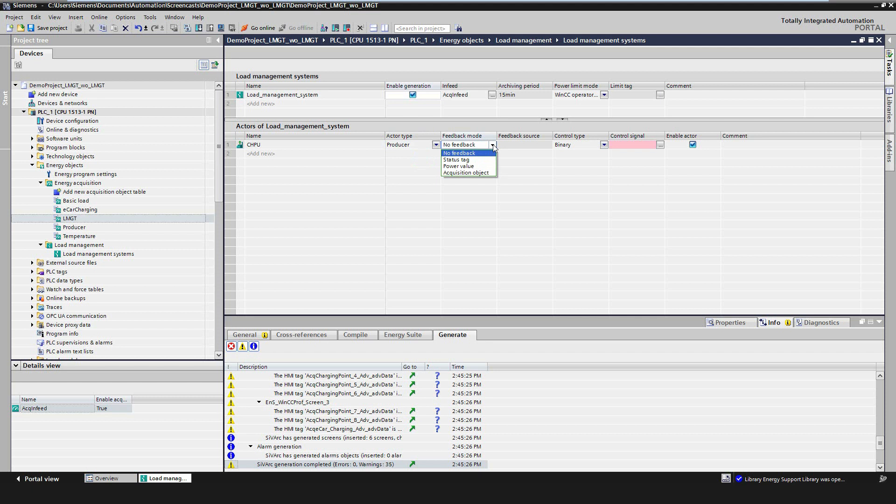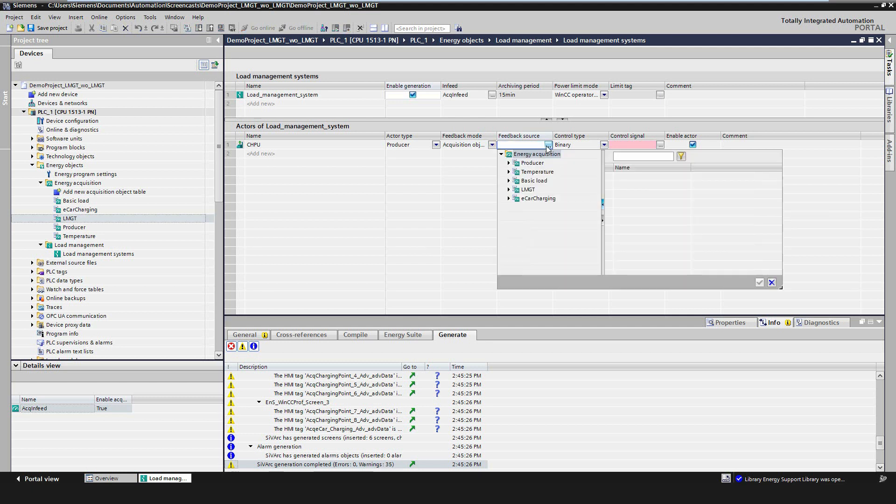There are four possibilities to get the feedback of the actor. First, a binary status signal, for example, the feedback signal from a switch. Second, an analog value, for example, the active power of a consumer or producer. Third, an acquisition object which has been created before. And fourth, completely no feedback, which is not recommended as the system gets absolutely no information about the current status of the actor.